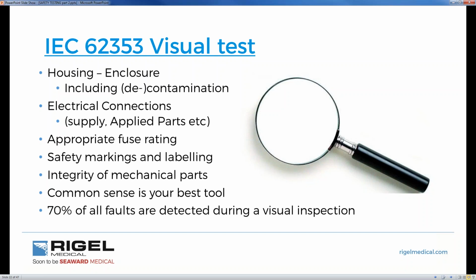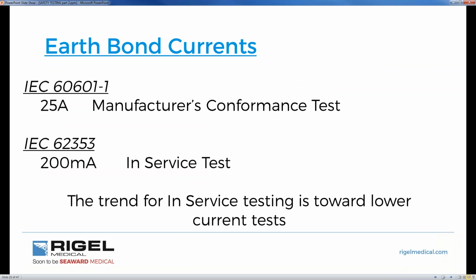If there's too much current being drawn because the device is faulty, then you could damage the device, but you could start a fire, etc., etc. So looking at the fuse rating is very important for a medical device or any electrical device. We look at safety markings and labeling, class 1, class 2, BF, CF, etc. We look at the integrity of mechanical parts to make sure they function as per intended purpose of use. And one major thing with the visual test, because it is the first test, is that 70% of all faults are detected during the visual inspection. We don't want to plug in a medical device that doesn't look right, doesn't look correct. It's very important. This is why it is the first test in the sequential order of 62353.